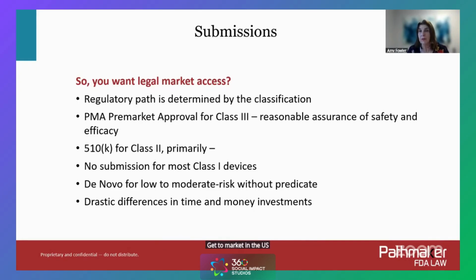510(k)s are by far the most common way that devices get to market in the US. There are about 3,000 510(k)s filed with FDA every year. It's primarily for well understood class 2 devices, and there is a myriad of different devices that fit into class 2. Most class 1 devices do not have to go through any sort of PMA or 510(k) premarket review. However, there are just a couple. I'll give you one example, and that's examination gloves. They're class 1, but examination gloves have become very important in protecting people from handling opioids or body fluids that may have pathogens in them.